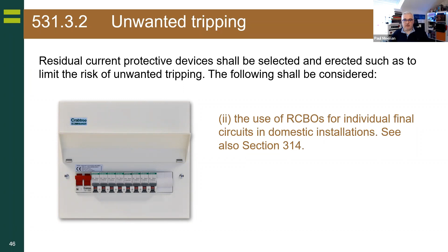For those who are probably thinking, what gibberish is he talking about when it comes to RCDs? So many, many moons ago, we all knew RCDs were a supplementary or additional method of protection. And regulation 531.3.3 introduces us to, obviously we know Type AC, which is for standard AC resistive or inductive loads, which is what we've been using for years. Type A was introduced in the 18th edition, and that protects against leakage up to 6 milliamps. And those 6 milliamps, what looks like two weird bumps in the road, is effectively a half-wave rectified DC. We need to learn what these little images are.